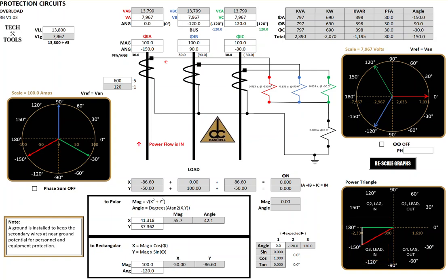I put the load on the other end in this case. Just change directions. A transmission line sees power flow changes like this all the time. So let's look at the other one. We originally had a -30 degrees. What do you think it would be to change that one in the opposite direction? 30 would have to become a 150. Just that simple. And B would have to become a 30, and then C would have to be a -90.